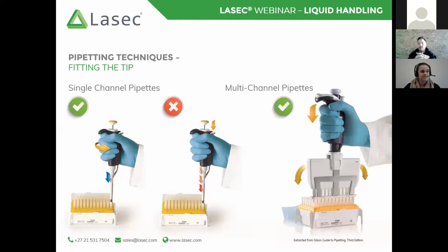This is also why, when changing volumes, it is incredibly important that you stick within the working range of the pipette. Should you exceed the working range, you may risk breaking the pipette by moving that piston further than where it can be. And therefore, you basically throw out all the accuracy and precision that you would have with that pipette. Okay, so I hope that video nicely showed you exactly how that piston moves up and down. As I was increasing that volume, it was in an anti-clockwise direction. I then had to pass it and rotate back clockwise down to the set volume that I wanted.